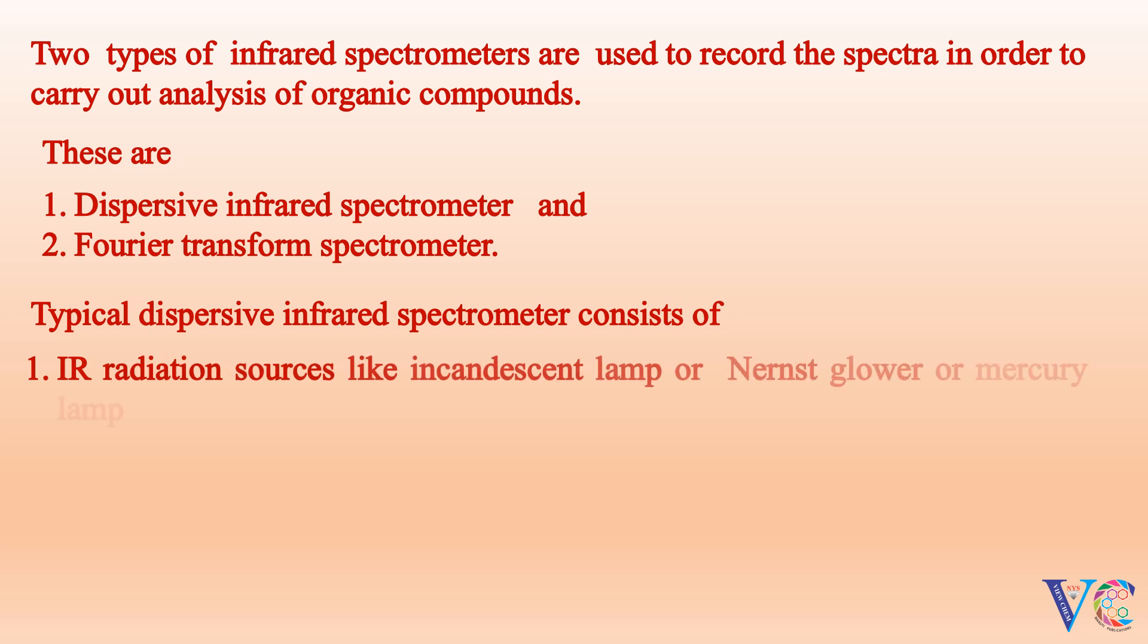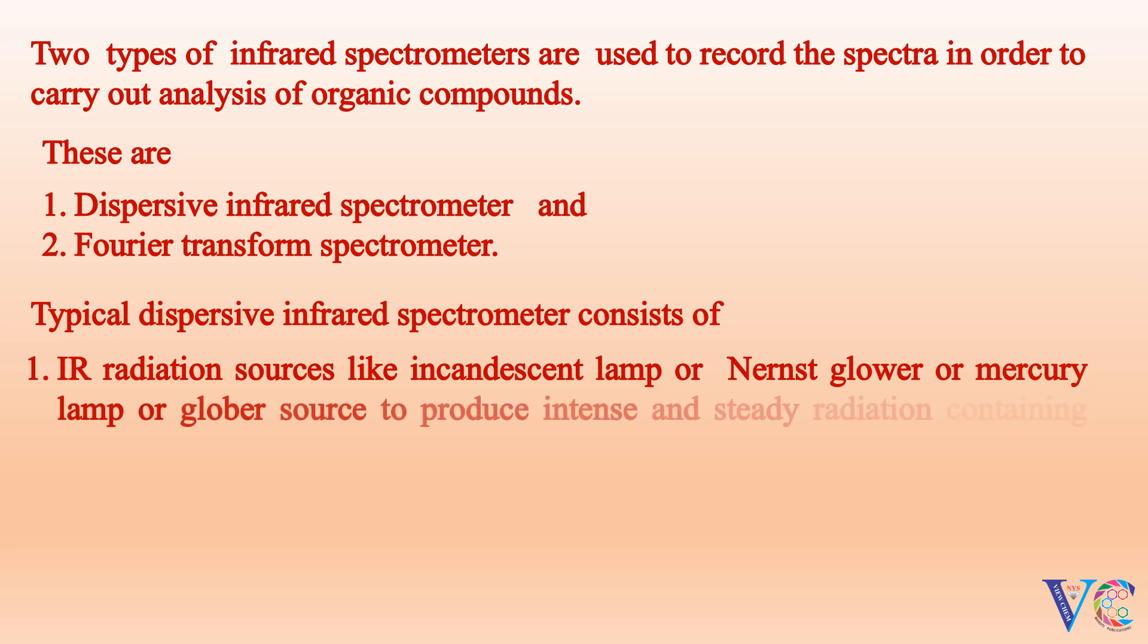Typical dispersive infrared spectrometer consists of IR radiation sources like incandescent lamp or Nernst glower or mercury lamp or Globar source to produce intense and steady radiation containing wide range of wavelengths.